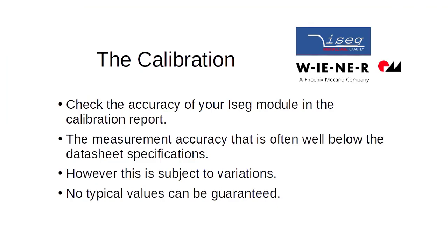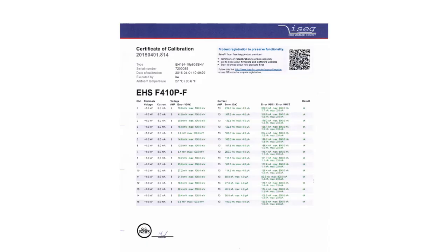A much faster way to check the accuracy of your Iseg module is to take a look at the calibration report. This report is delivered with every purchased module. In general, the error measured after calibration is well below the maximum error given in the datasheet specification. However, this is subject to variations of the production process and the used components. Therefore, it is impossible to guarantee typical values for measurement accuracy.